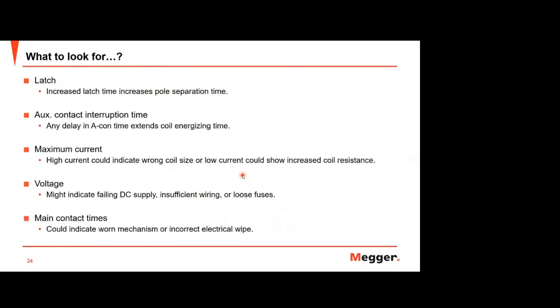What to look for? This is some information. Maybe I will explain some definitions after this slide. With the latch information, you can estimate the problem on latch time, because this latch time issue will affect the total time. So increased latch time increases pole separation time, and also auxiliary contact interruption time. Any delay in the auxiliary contact time will extend coil energizing time.